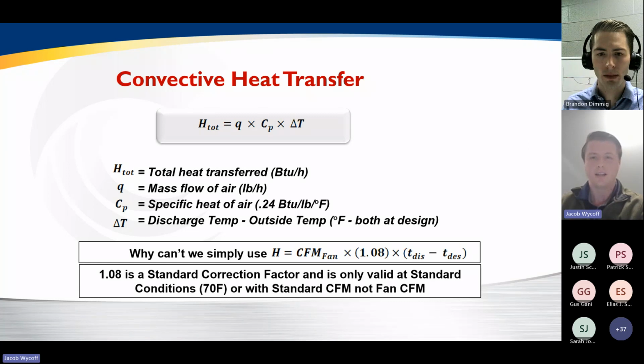The final takeaway that I'm going to try to prove to you guys is that an HTHV unit is able to provide 127% more net or usable BTUs per CFM through that constant volume fan compared to a draw-through unit at 120 degree discharge temperature.